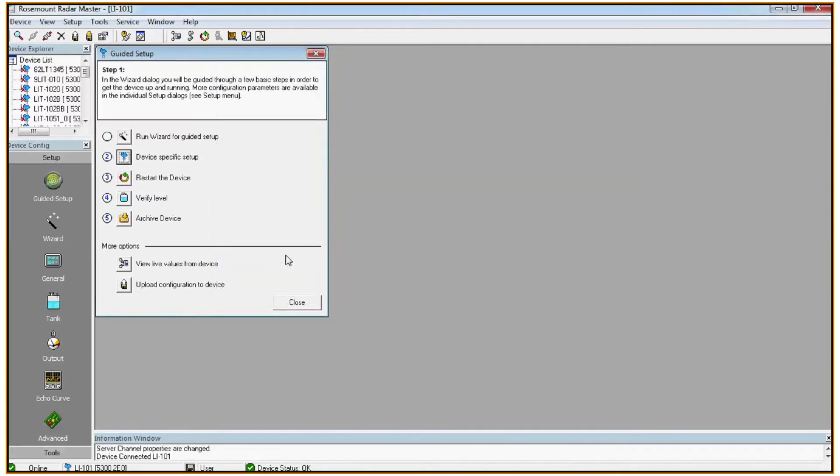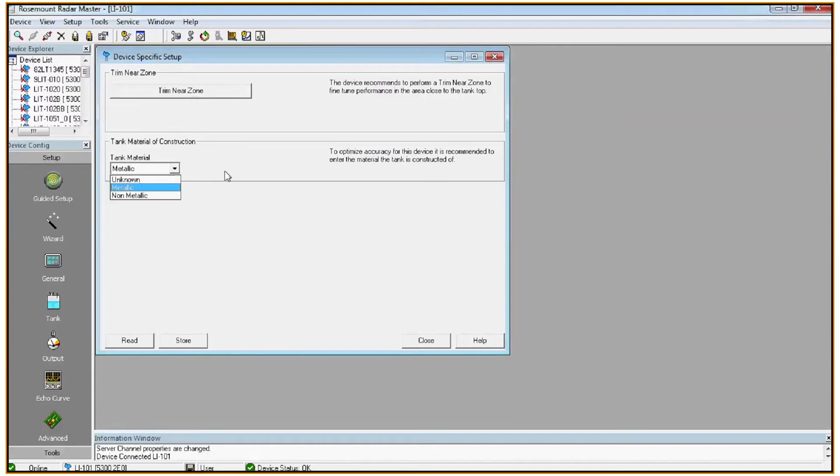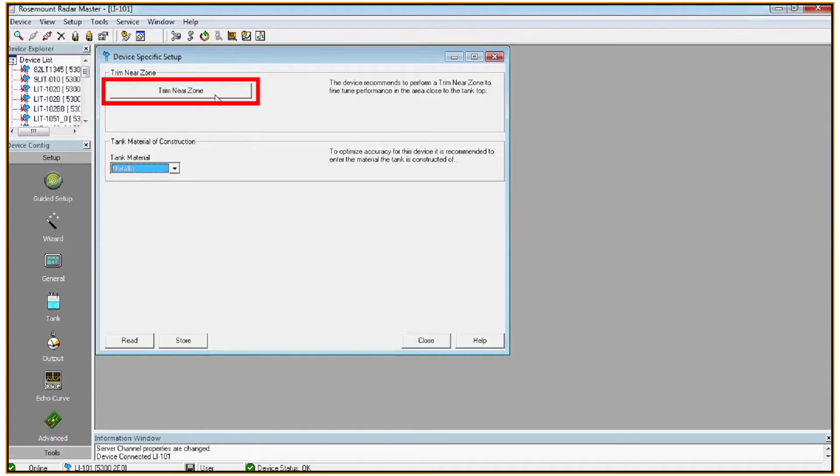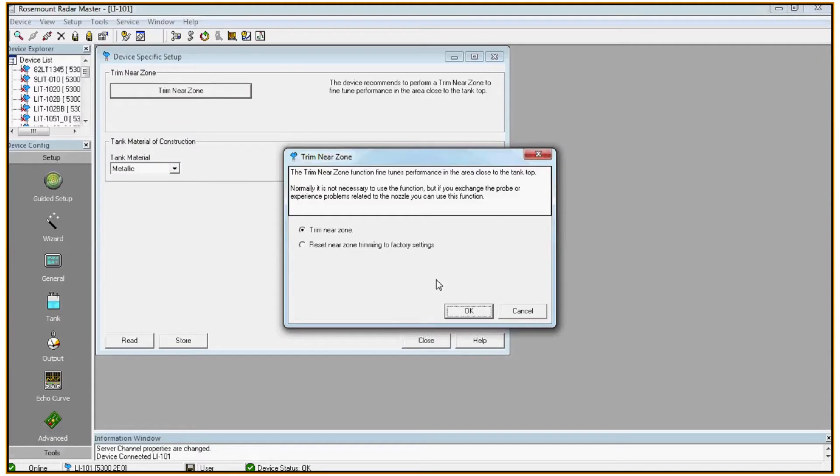Now that we ran through the wizard, most of the key configuration parameters are taken care of, but there are a few more things we'd like to check. We'll next go into device specific setup. We want to make sure that we select the right tank material. In this case we'll go with metallic. And if the tank is empty or if there's no product touching the probe, you can do a trim near zone. Hit OK.